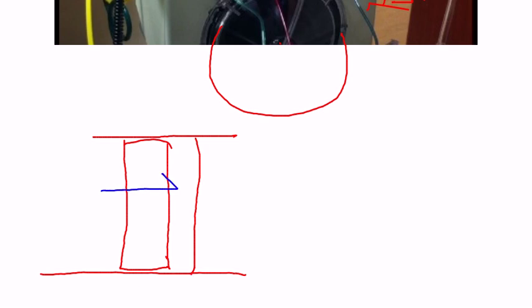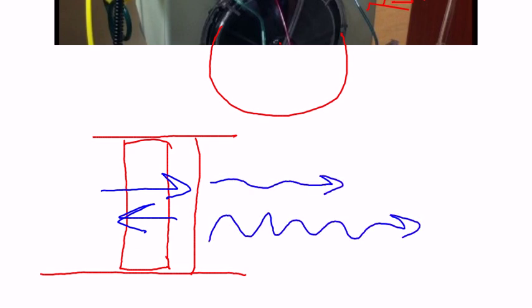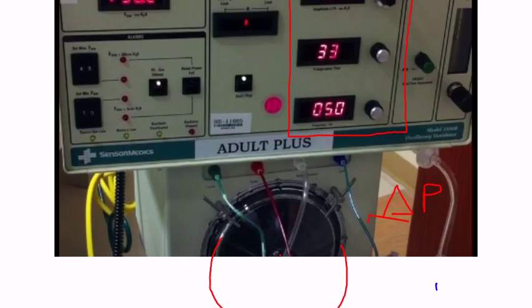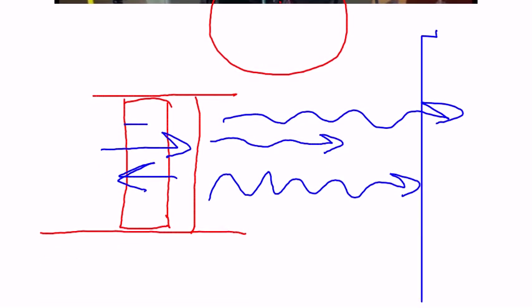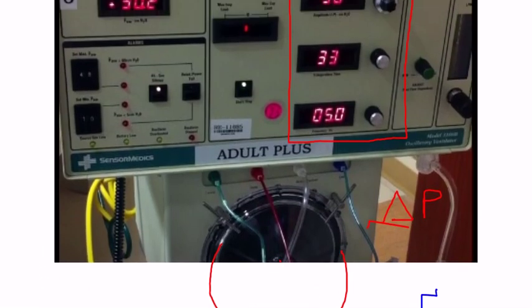The piston oscillates back and forth very quickly, and on the other side of that rubber seal, I have the air that is oscillating going into the patient. What that delta P does is it basically changes how much displacement I have — if I have very low delta P, the little piston is not going to move very much. At a very high delta P, the piston is going to move more, so I'll be able to move more bulk amounts of air by changing the delta P. So that's my power.